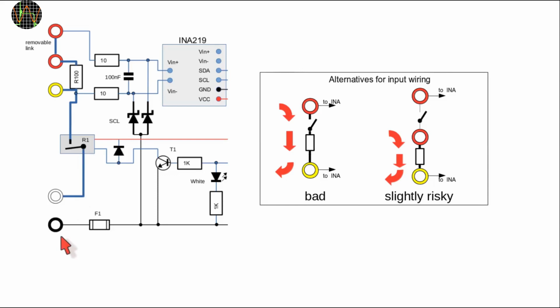This arrangement allows me to use different shunts if I want to measure higher currents. For example, I already have a 5 milliohm shunt. To use it instead of the internal 0.1 ohm shunt, I remove the link between the two red terminals and connect the external shunt between the top red one and the yellow terminal.